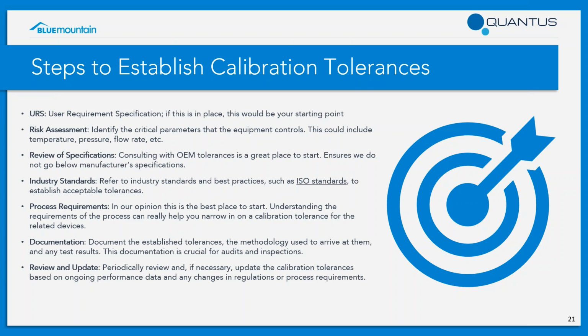This is a really important part of the process to understand the criticality of the device. You're going to want to focus on the parameters of the equipment controls. In general, items that have a higher risk would have a lower tolerance related to the process, and conversely, items that have a lower risk are allowed to have a little bit wider tolerance. Again, for reviewing specifications, we're going to recommend consulting the manufacturer's tolerances. And just as important as making sure it's not too tight for the process, we also want to make sure that we're not setting a tolerance that's below manufacturer specifications.